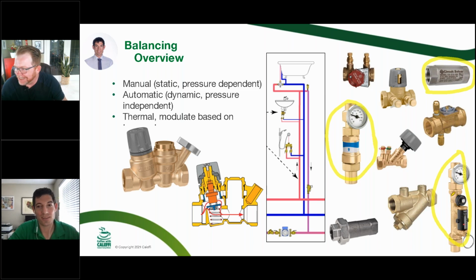Well, it depends on how expensive your balancing contractor is, because that valve, again, you take a wrench and you adjust it, and then you pull that pin and you verify your flow rate, and you're done. We have a high-rise project in Florida, and he's like, I'm going to get off of this job a month earlier because I don't have to send a balancing contractor to every single unit in this high-rise construction. So they're going to do the thermosetters, set the temperature, and then they go back down the elevator and move on to the next job. So again, it comes back to what your labor is worth. Someone will beat you on price with a manual balancing valve, but they may not beat you on the overall cost of that job.